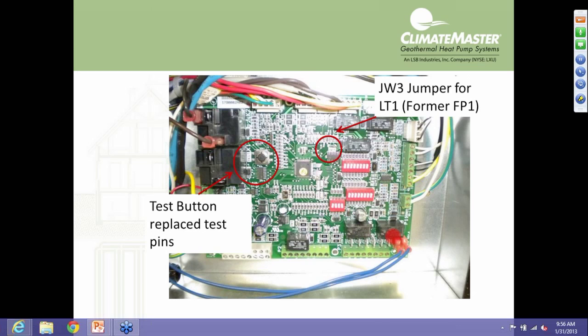On the board, a couple other items. The test mode in this board is now a button. You press the button. And there's also a jumper on the board. The JW3 jumper is for our LT1 freeze protection sensor between the TXV and the coax, formerly called FP1 in some of the previous products.